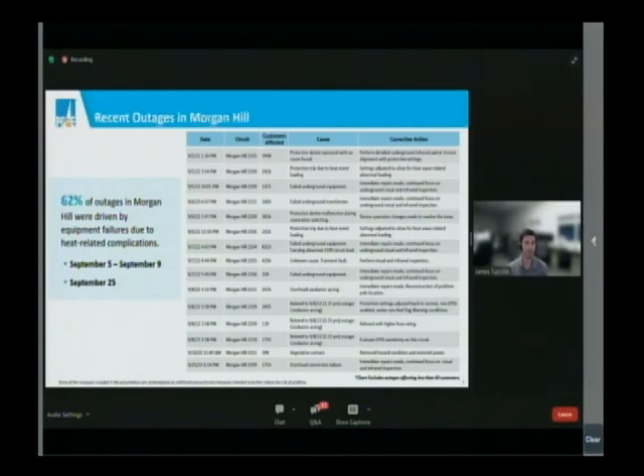EPSS is a relatively new program to PG&E, since late August 2021. We've expanded it tremendously. My team is in charge and responsible for the engineering that goes into these settings. And I can assure you that we are optimizing our fire risk prevention while still enabling the most reliable service that can be provided. And so as we see these events, as we learn, as we understand how the system reacts, we're taking measures to mitigate these impacts. These settings, this method of protection on the system, has never been introduced at the scale anywhere in the country that PG&E has embarked on.